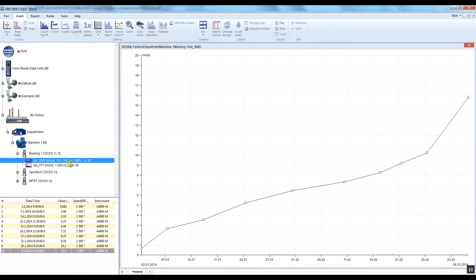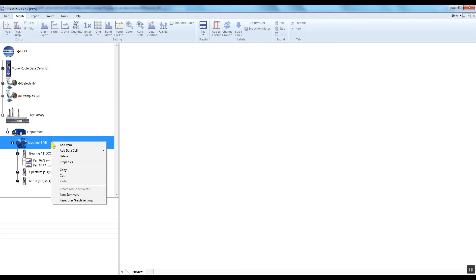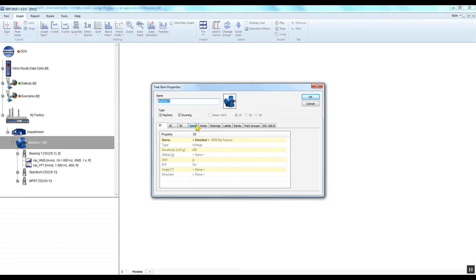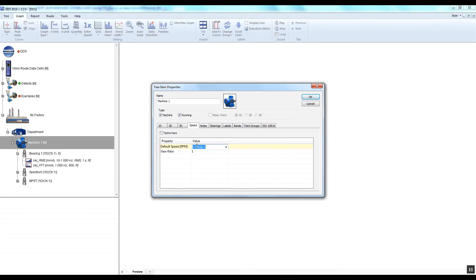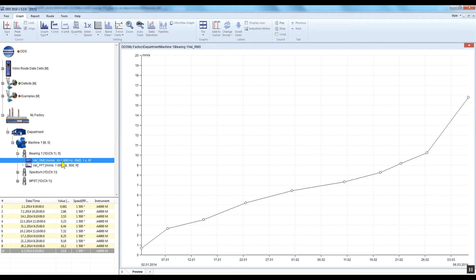The Adash alarm limits require information about the speed. You can set the speed under the required machine or measurement point — right-click on the required machine or measuring point, select Properties, and go to the Speed tab. Enter the speed value and confirm by clicking OK. However, the speed measured by the instrument has priority. For the Vibrio M, the speed will be taken from the first screen auto speed detection or manual input. For the VA3 Pro or VA4 Pro, it is taken from the speed probe.